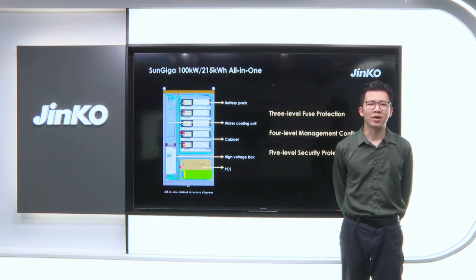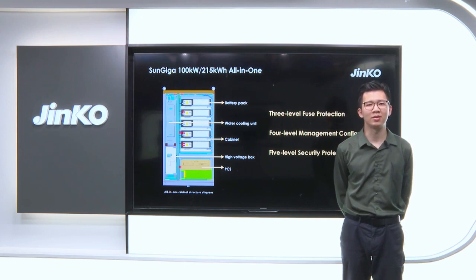48 batteries are connected in series to form a pack, and each all-in-one cabinet is made up of 5 packs connected in series. The AC side adopts a 100 kilowatt PCS, which can continuously and stably deliver 400-volt AC power to the grid.